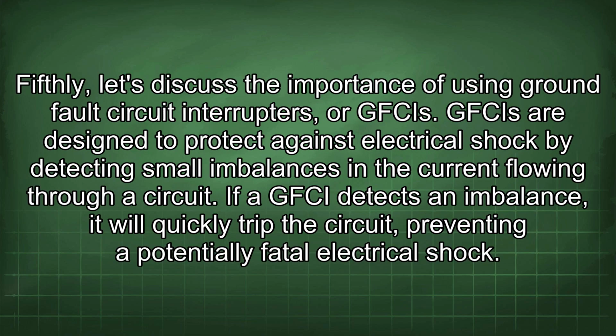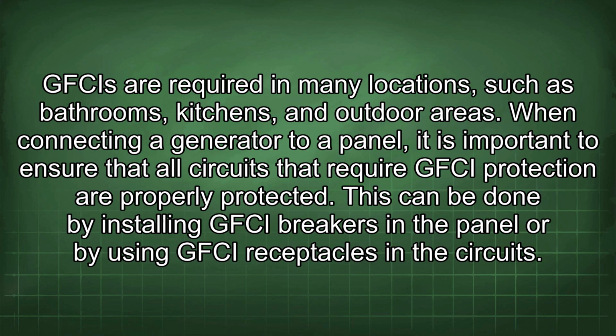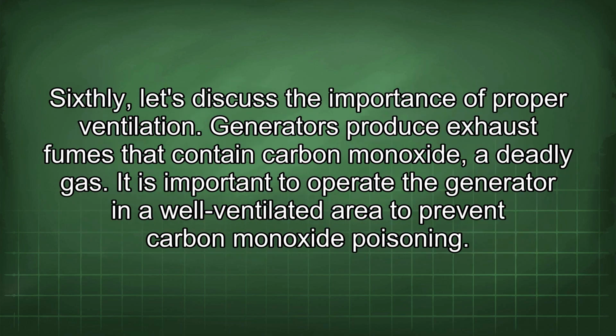Fifthly, let's discuss the importance of using ground fault circuit interrupters, or GFCIs. GFCIs are designed to protect against electrical shock by detecting small imbalances in the current flowing through a circuit. If a GFCI detects an imbalance, it will quickly trip the circuit, preventing a potentially fatal electrical shock. GFCIs are required in many locations, such as bathrooms, kitchens, and outdoor areas. When connecting a generator to a panel, it is important to ensure that all circuits that require GFCI protection are properly protected. This can be done by installing GFCI breakers in the panel or by using GFCI receptacles in the circuits.